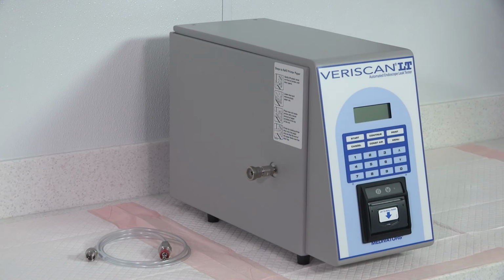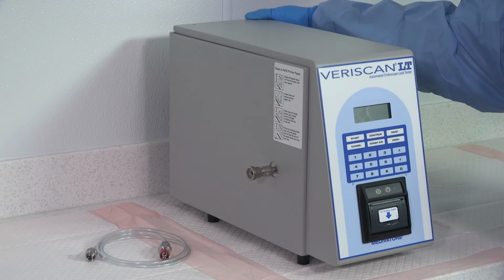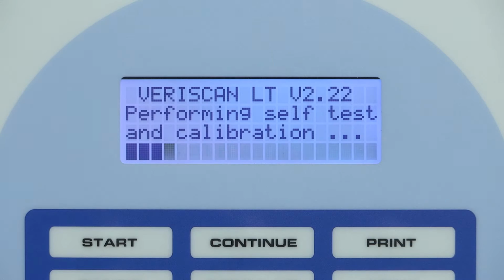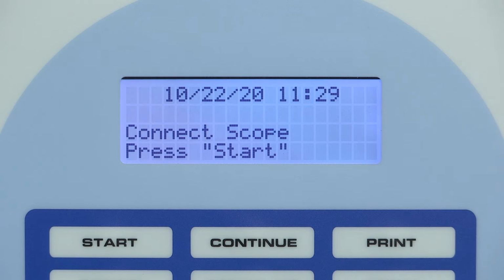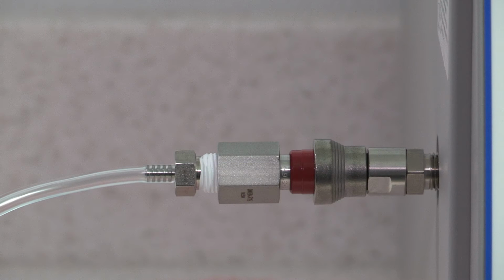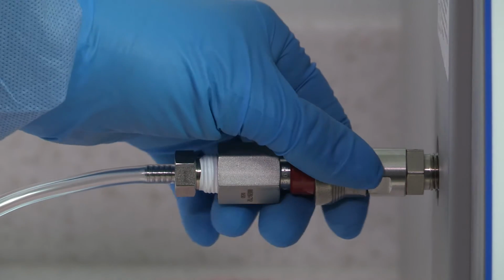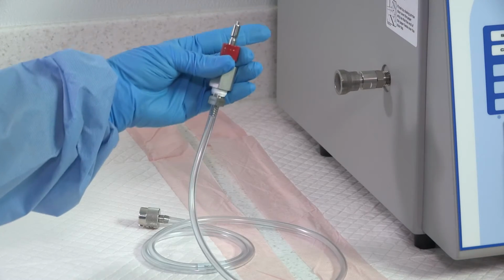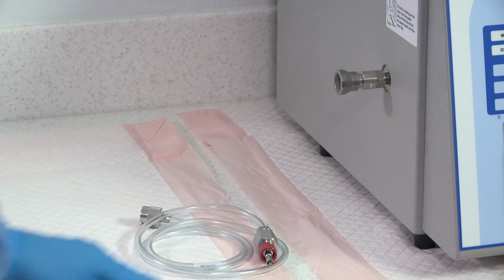First, press the power switch located on the back of the unit to turn it on. This automatically performs an initialization process that includes a series of diagnostic self-tests. When the process is complete, the display shows the current date and time and indicates that you can connect an endoscope and press Start. The daily quality assurance test must be performed without the quick connect tubing or endoscope attached. If the quick connect tubing is still attached, remove it from the quick connect port by pulling outward on the quick connect port's outer metal housing until the quick connect tubing is released.